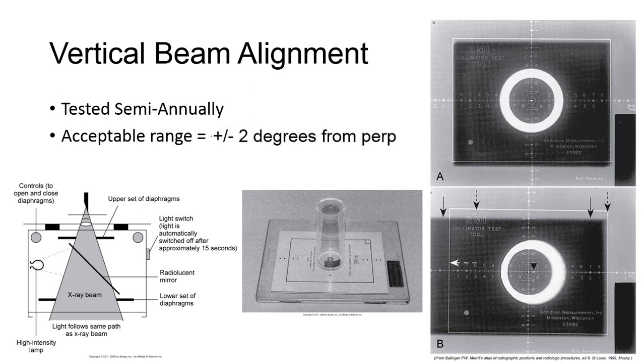This test tool allows for collimator alignment, vertical beam alignment, and a third test, central ray alignment, all in one exposure. The central ray should simply be pointed at the crosshairs on the center of the tool, where the BBs would be lined up, and the exposure should be accurate within ±2 centimeters from the light field's central ray.